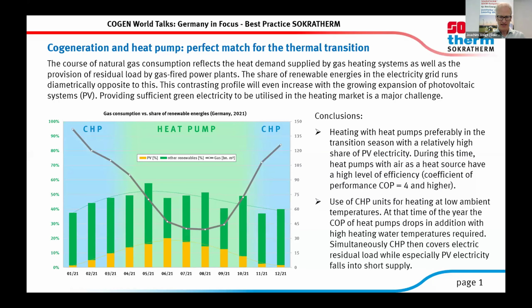And on the other hand, CHP units should preferably be used in the wintertime at low ambient temperatures. At that time of the year, the COP of the heat pump drops, in addition to the high heating water temperature required in the heating network. So on the one hand, heat pumps have poor efficiency in winter, so you use CHP instead, and simultaneously the CHP then covers the electric residual load, which is especially needed in the wintertime, as was explained before.